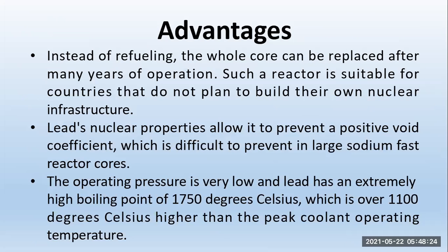Advantages: instead of refueling, the whole core can be replaced after many years of operation. Such a reactor is suitable for countries that do not plan to build their own nuclear infrastructure. Lead's nuclear properties allow it to prevent a positive void coefficient, which is difficult to prevent in large sodium fast reactor cores. The operating pressure is very low, and lead has an extremely high boiling point of 1750 degrees Celsius, which is over 1100 degrees Celsius higher than the peak coolant operating temperature.